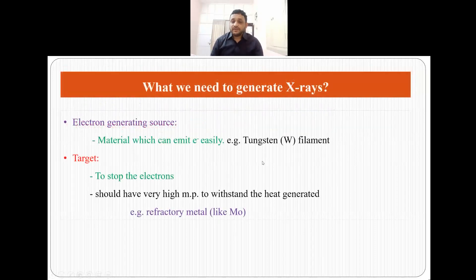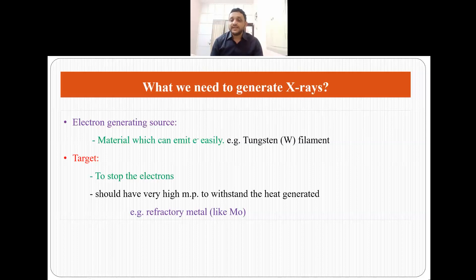To generate x-rays we need two things. First is an electron generating source, which is made up of material that can emit electrons easily, like a tungsten filament. Second is the target, which should be able to stop the electrons and must have a very high melting point to withstand the heat generated. That is why the target is made up of a refractory metal like molybdenum.